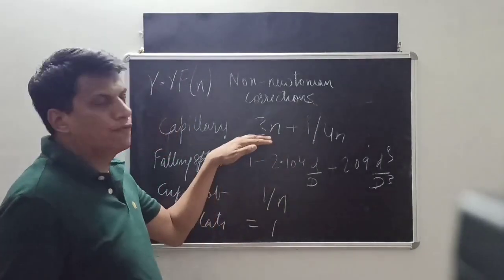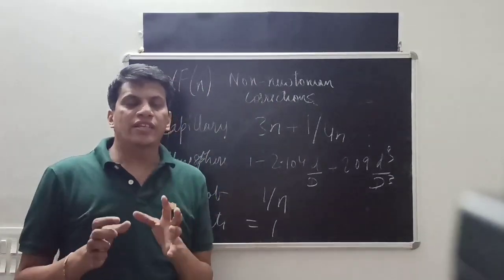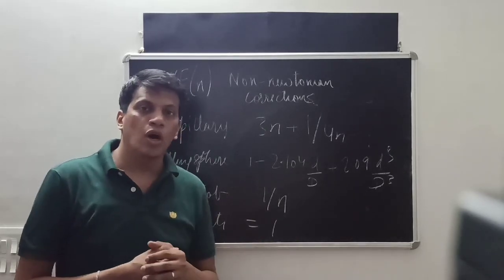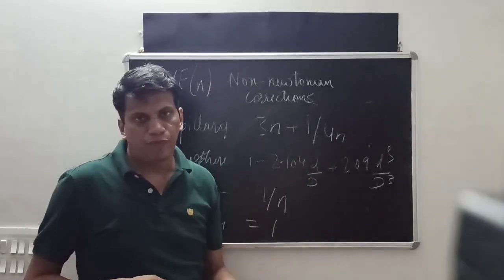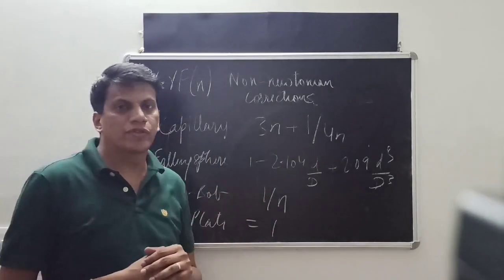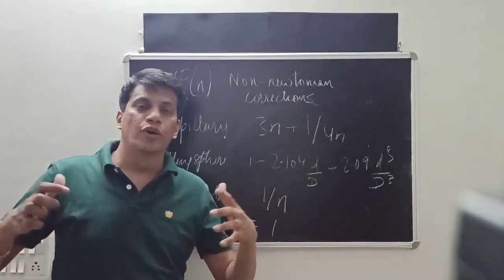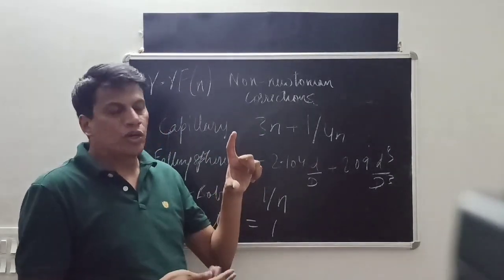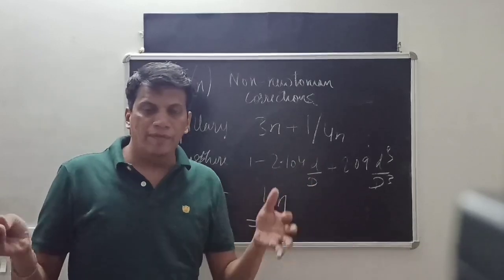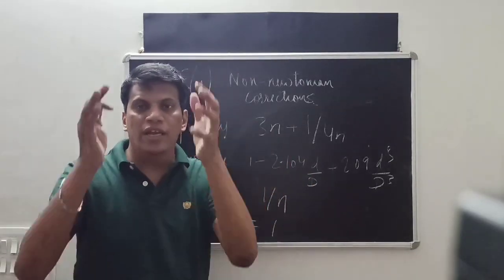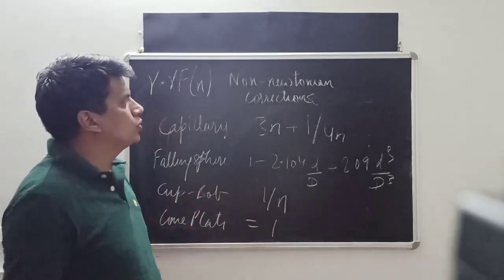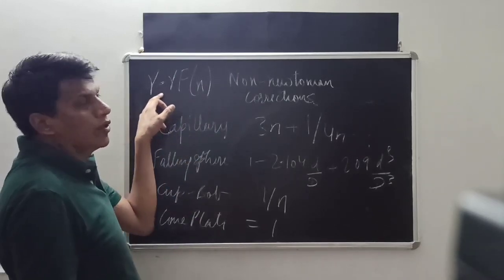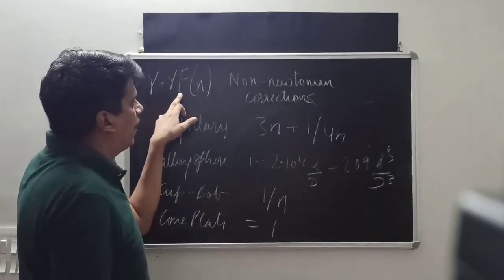The last part of viscometers is non-Newtonian corrections. Capillary viscometers are based on Poiseuille's equation, and falling sphere viscometers are based on Stokes' law. Poiseuille's equation assumes liquid flows freely through a capillary, and Stokes' law assumes the fluid is infinite with no obstructions. In practice, however, the liquid is not falling freely due to pressure, and the fluid is constrained by container walls. Because of these deviations, non-Newtonian correction factors must be included.